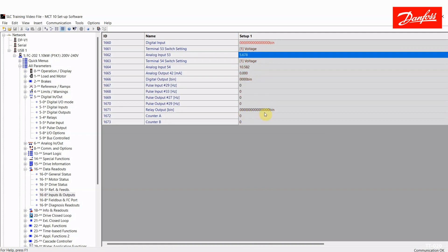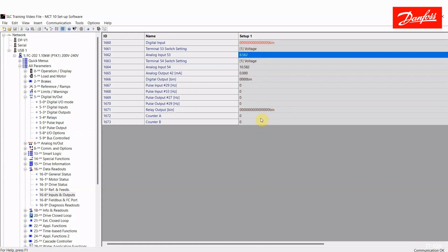So I've said when this becomes greater than 9 volts that comparator 0 will be true and relay 1 will activate. Right now, no relays are active. We'll get close to 9 volts and the relay has still not fired. Now, we'll cross the threshold here and you will see that that relay will become active. So this bit right here is indicating that relay 1 is changing states as I go above and below 9 volts. So that is a comparator. You can use those comparators and attach them to outputs or also use them in the sequence.